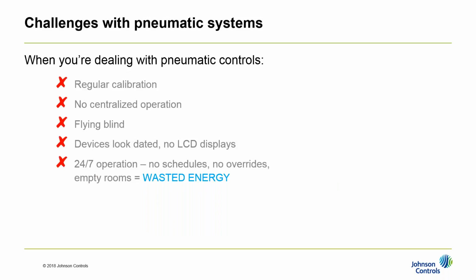So, as I've touched on, pneumatic thermostats require regular calibration to avoid ongoing discrepancies between set point and actually experienced temperature. You're not typically going to have any centralized operation with these systems. If you want to know what's going on in the zone, you have to go to the zone. You're flying blind.